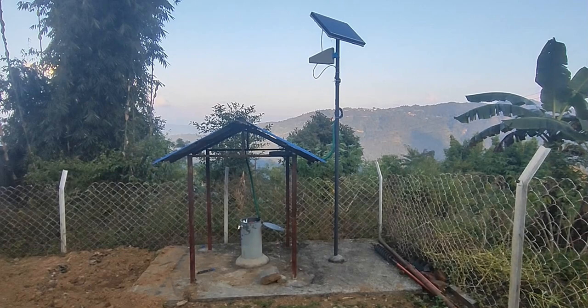And most importantly, this particular station should be far away from the noises that are made by the humans. So you see this vegetation here, this vegetation is just covering, and there is no kind of vehicle movement or human movement at this place. And this fence is also made to avoid entry of any animals in this. And then the access is also very important. Sometimes if there is an issue, you need to go to that place and then do the maintenance.